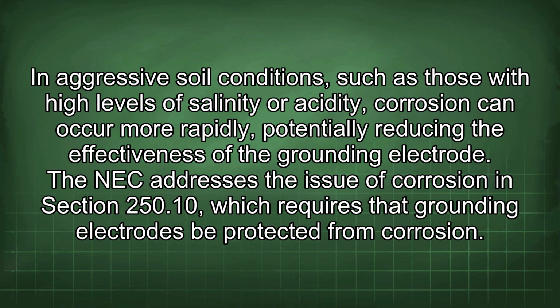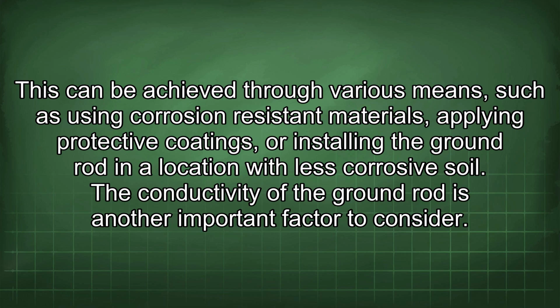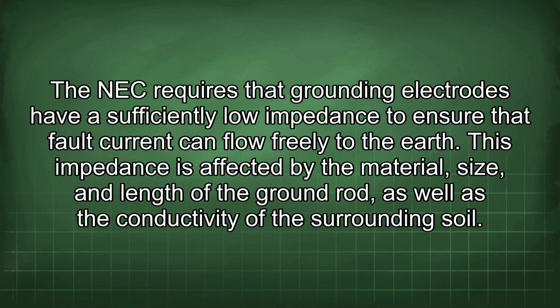The NEC addresses the issue of corrosion in Section 250.10, which requires that grounding electrodes be protected from corrosion. This can be achieved through various means, such as using corrosion-resistant materials, applying protective coatings, or installing the ground rod in a location with less corrosive soil. The conductivity of the ground rod is another important factor to consider. The NEC requires that grounding electrodes have a sufficiently low impedance to ensure that fault current can flow freely to the earth. This impedance is affected by the material, size, and length of the ground rod, as well as the conductivity of the surrounding soil.